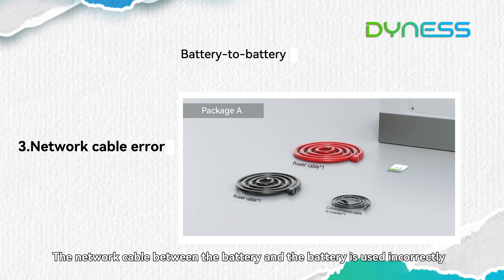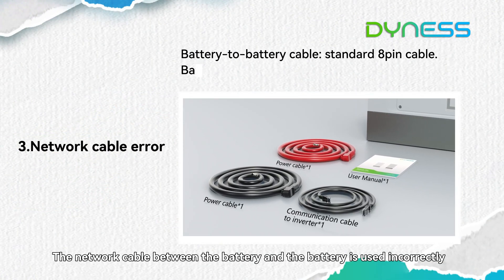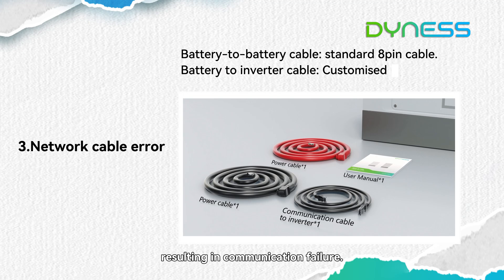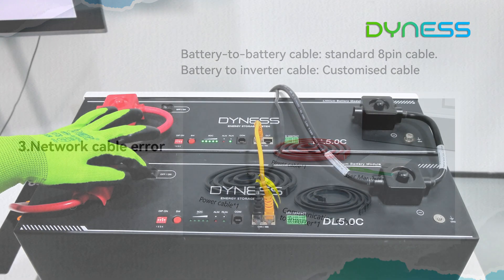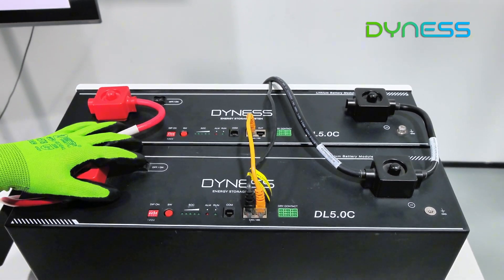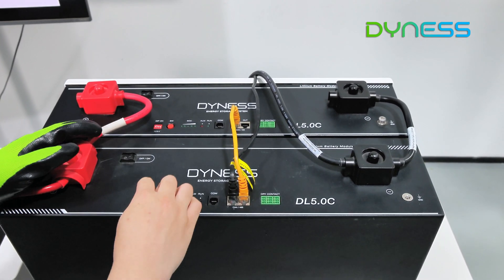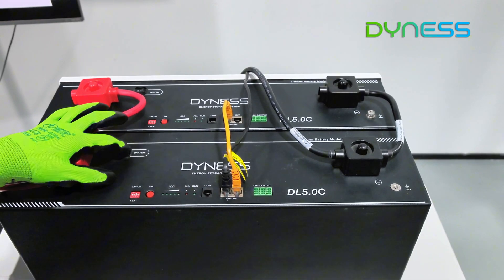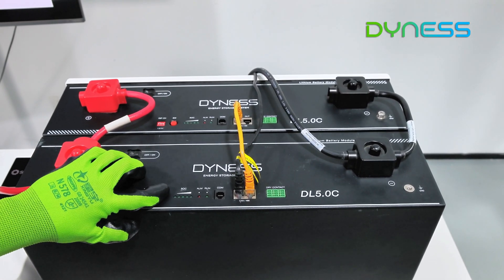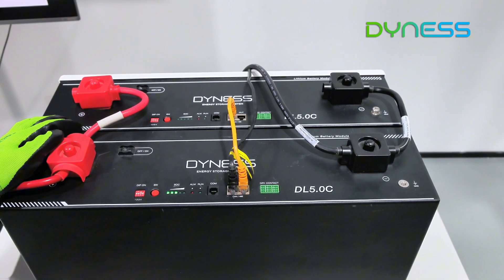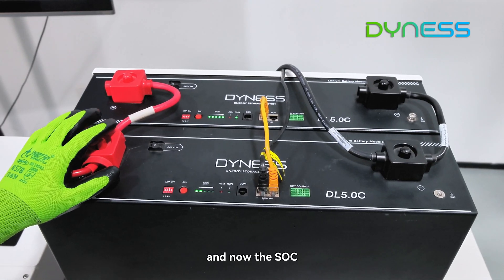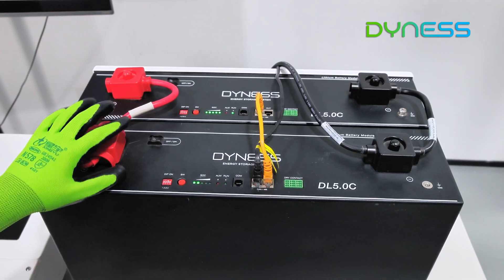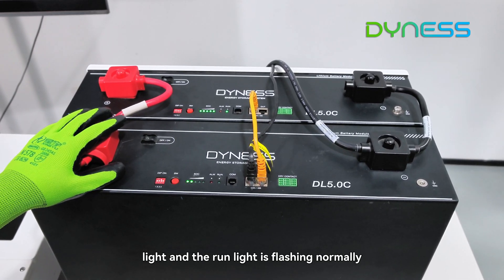The network cable between the batteries is being used incorrectly, resulting in communication failure. The solution is to refer to the product instruction manual and follow the wiring connection guidelines. After correcting the wiring, the SOC light and the RUN light will flash normally.